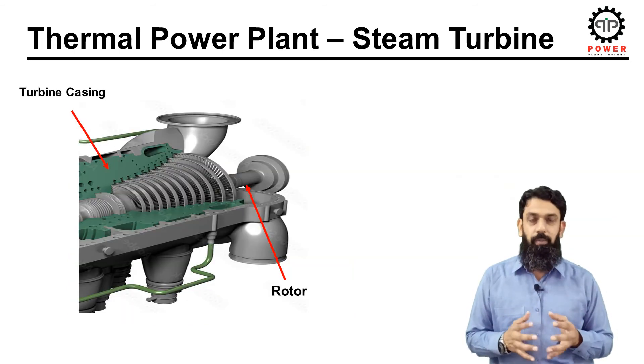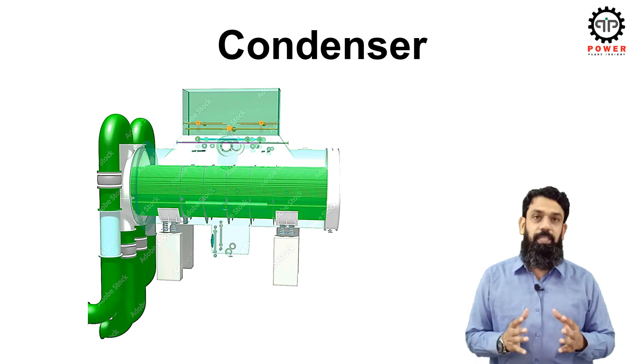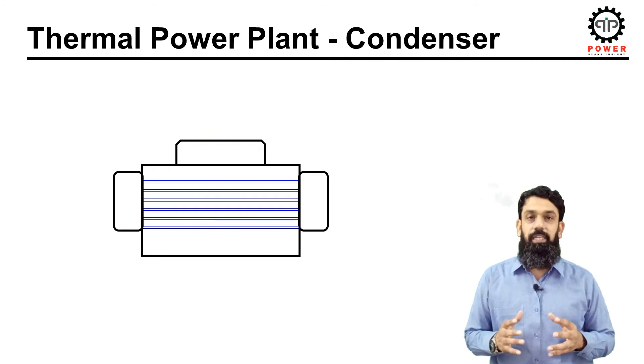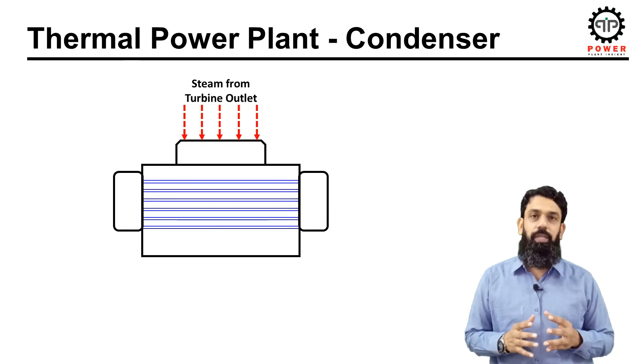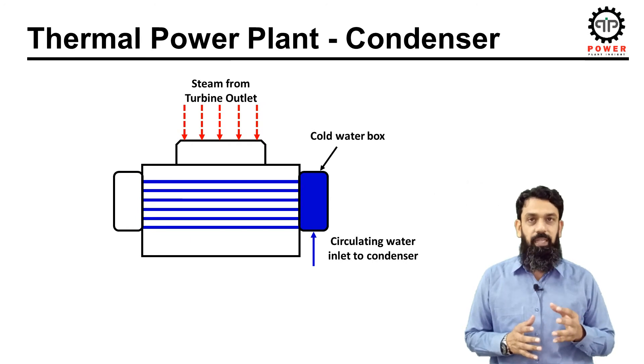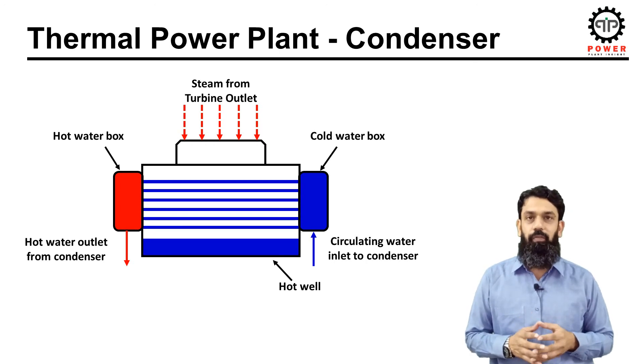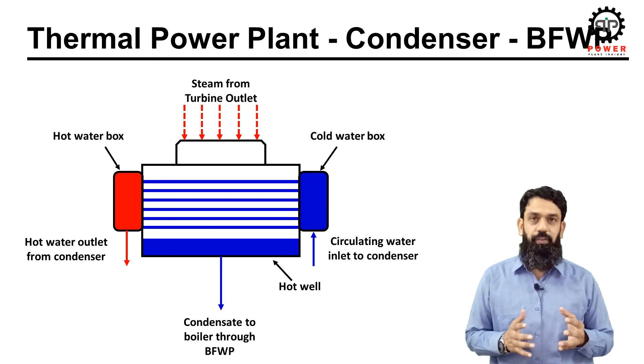This is how the rotor fits into the turbine casing with fixed blades and rotor blades. The condenser is one of the most important components in thermal power plants — it basically acts as a heat sink in thermal cycles and is one of the main components affecting plant performance. The condenser is a shell-and-tube type heat exchanger. Steam after doing its useful work in the turbine is routed to the top of the condenser on the shell side. Circulating water enters the tubes of the condenser through a water box and, after effective heat transfer, returns to the cooling tower as hot water. The steam condensate collects at the bottom of the condenser, which is called the hot well. Condensate from the hot well is extracted through boiler feed water pumps — high pressure feed water pumps — and injected into the economizer section of the boiler, and the cycle continues.